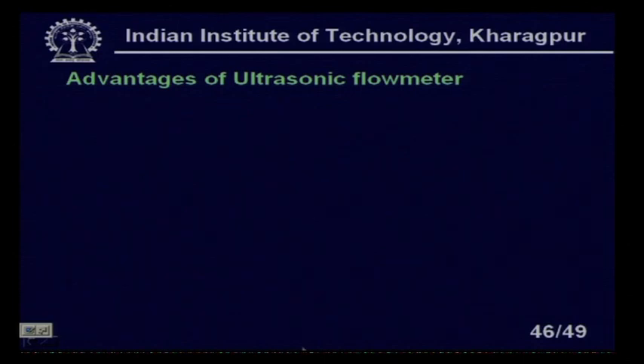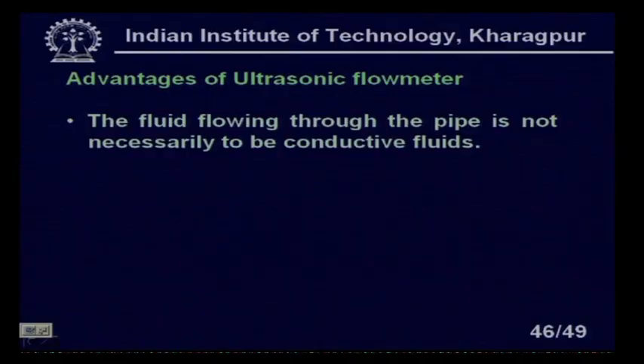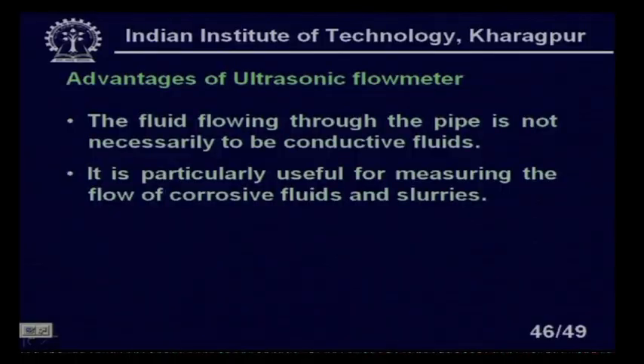The advantages of ultrasonic flow meters in general are: the fluid does not need to be electrically conducting — unlike the electromagnetic flow meter — making it particularly useful for corrosive fluids and slurries regardless of conductivity. It is a non-invasive method with significant advantages: it clamps on externally to existing pipe rather than being inserted as an integral part of the flow line.